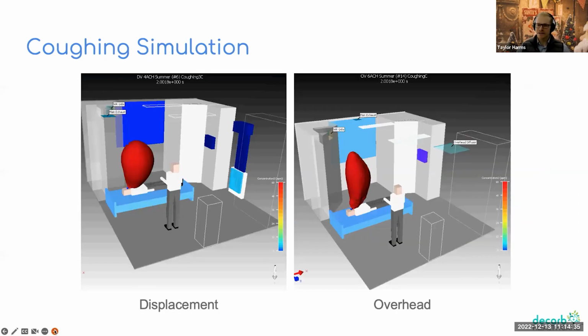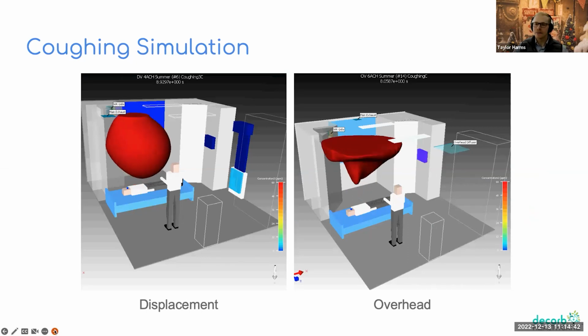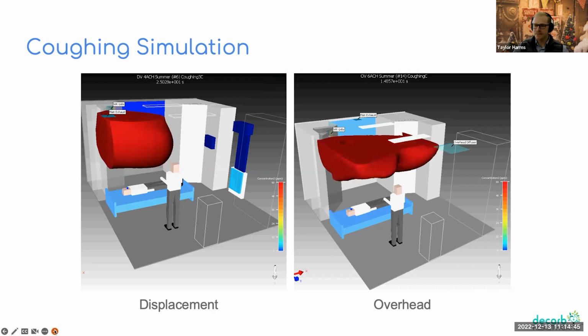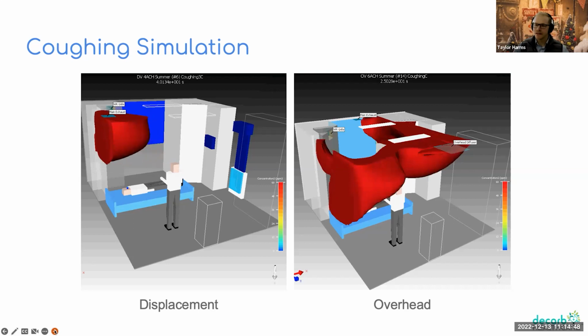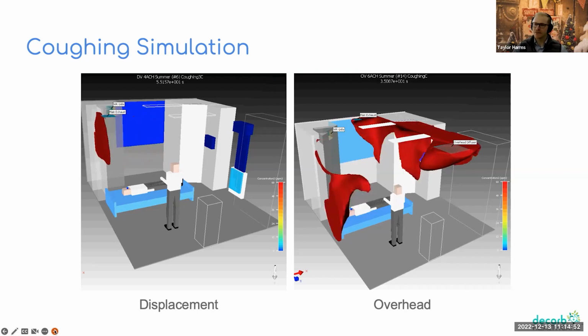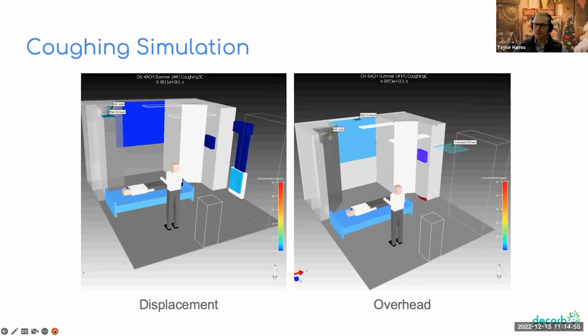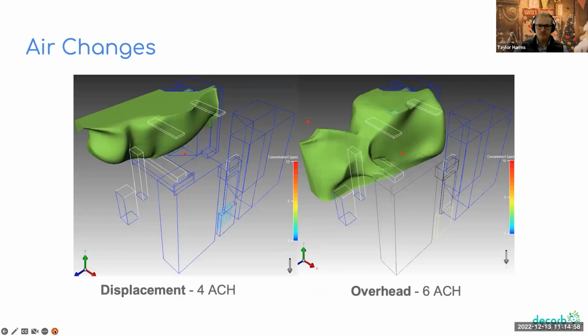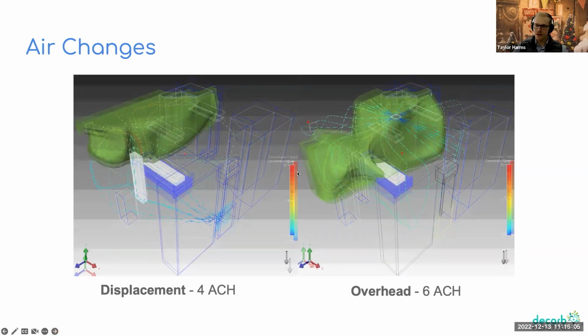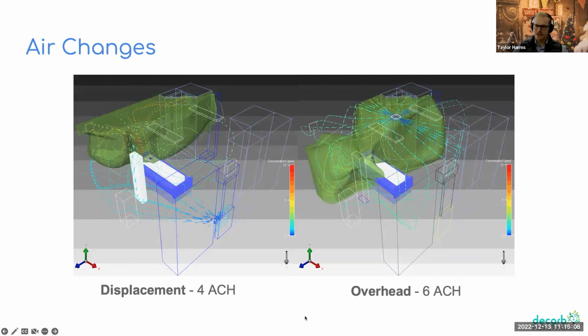Next slide. Here we can see a little bit of a demonstration of how it works. The contaminated air is brought out of the space much more quickly and isn't being mixed in with the rest of the air that's in the room, protecting the occupants inside. And something similar here as well. There's 2 less air changes required for the same amount of ventilation and contaminated air removal, comparing displacement ventilation to overhead mixing.